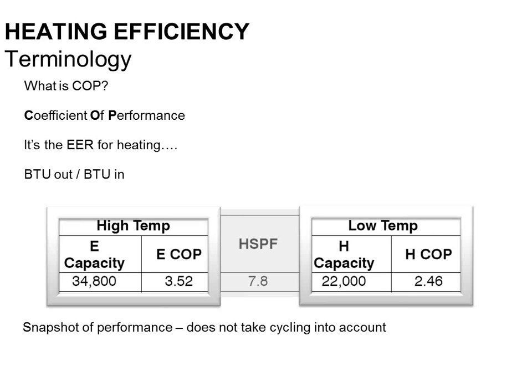Sometimes you'll see it listed as the 47 number and 17. Sometimes you'll see it as ECOP and HCOP. Those are the same things. There's lots of different numbers other than 47 and 17 you can rate at, but E and H are the two rating points that are most commonly used. So you'll see those mentioned down here. In this particular case, the HSPF of this heat pump is 7.8, which is a legal minimum heat pump.